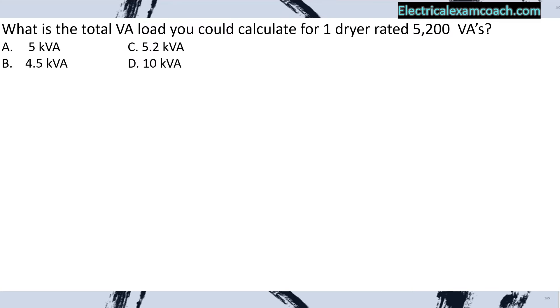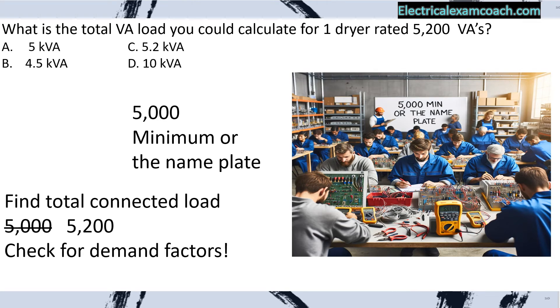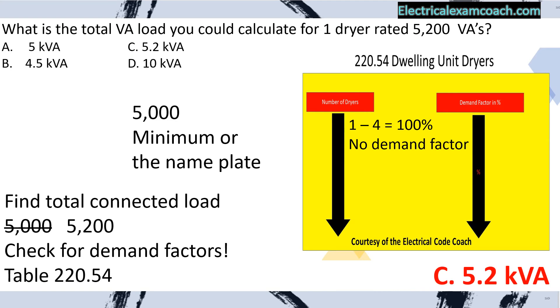What is the total VA load you would calculate for one dryer rated at 5,200 VAs? We find our total connected load using the 5,000 VA minimum or the nameplate, whichever is larger. In this case the nameplate is larger, so we select 5,200 VAs. We then check table 220.54 and find that for one to four dryers it's calculated at 100% — there is no demand factor. Answer: C.